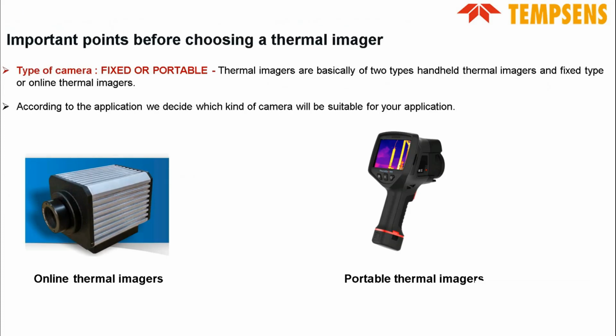Now, before choosing a thermal imager for your application, you should keep in mind the following important points that we are going to discuss in the coming slides, like type of camera, fixed or portable. Thermal imagers are basically of two types: handheld thermal imagers and fixed type thermal imagers. According to your application, we should decide which kind of thermal imager is suitable. Fixed type is basically used for continuous monitoring or critical applications which require 24/7 monitoring, and portable equipment is used for applications which require only scheduled maintenance.